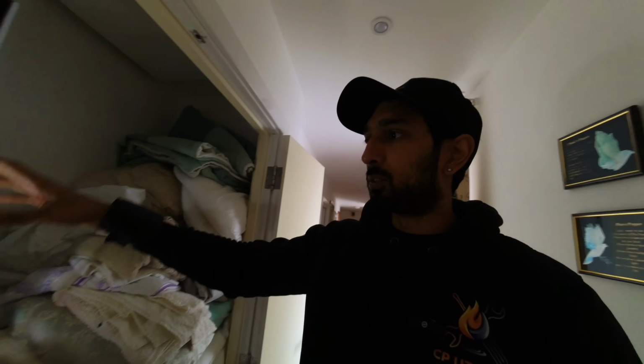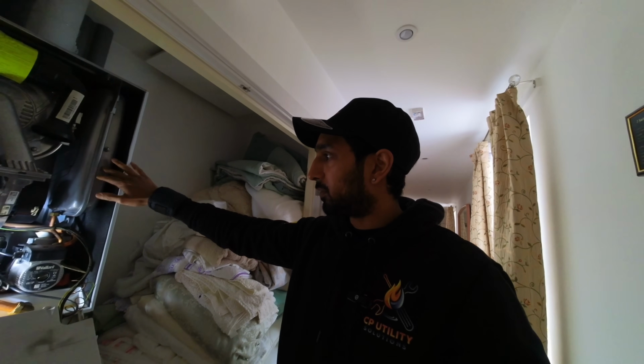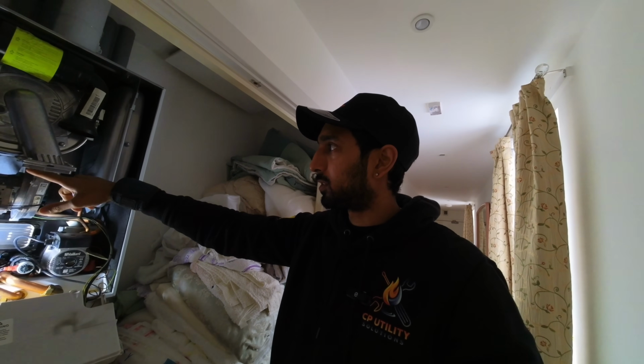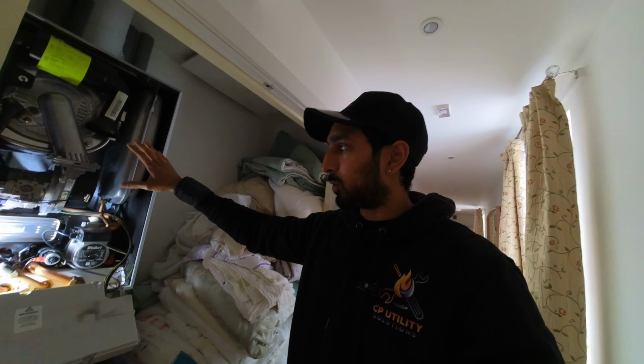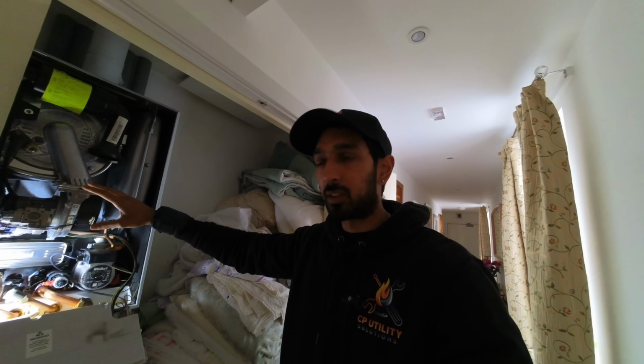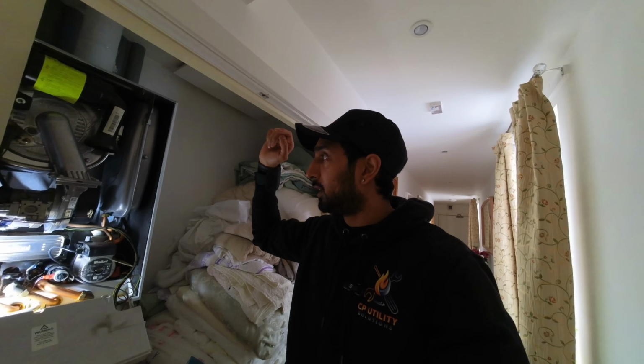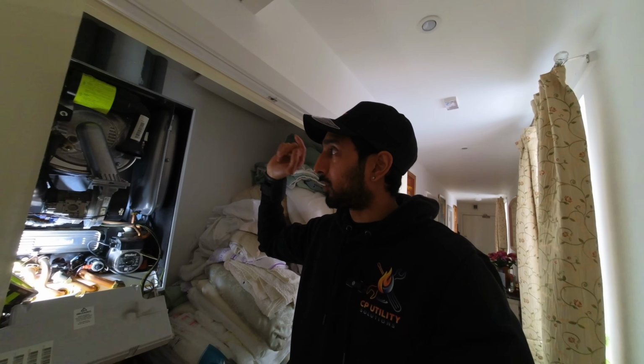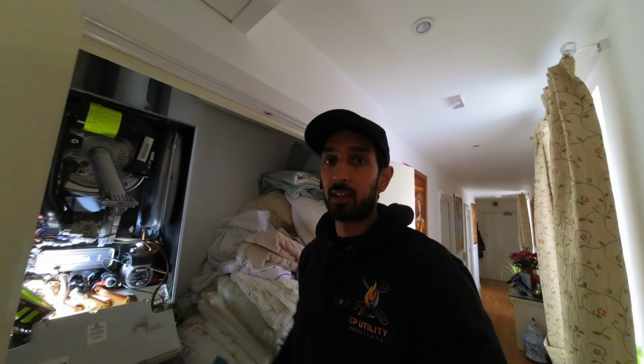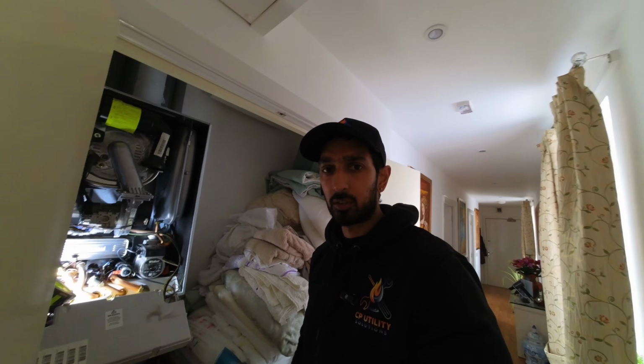So let's get the burner out. First thing I always do is the wet side first. I'm going to drain the boiler out, recharge the vessel, check the pressure charge on the pressure sensor, do all that stuff, get it back on, get it purging as well. I've already done a drop test, the gas meter's in a cupboard downstairs, so that's all good. While it's doing its purge program, I'll get that open and start cleaning it up, and change the condense hose as well. So let's get to it.